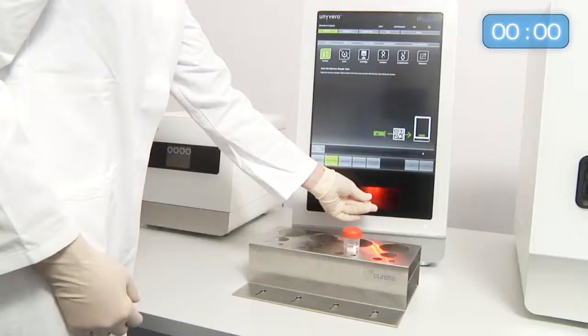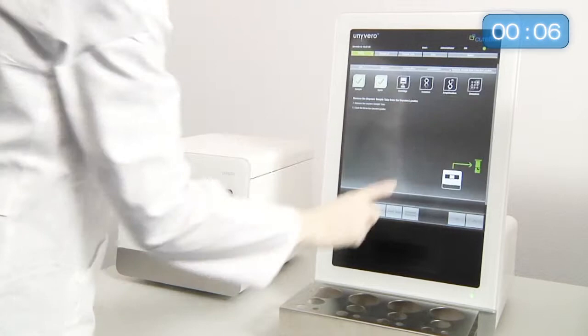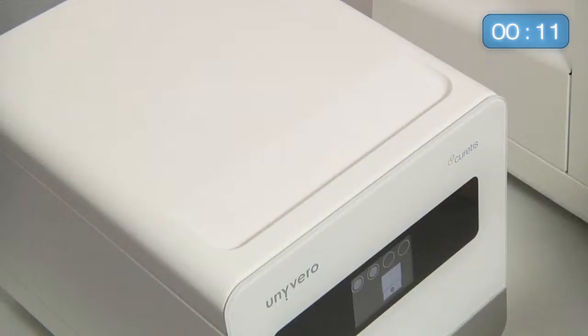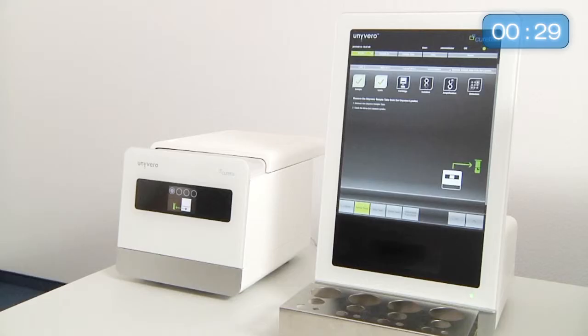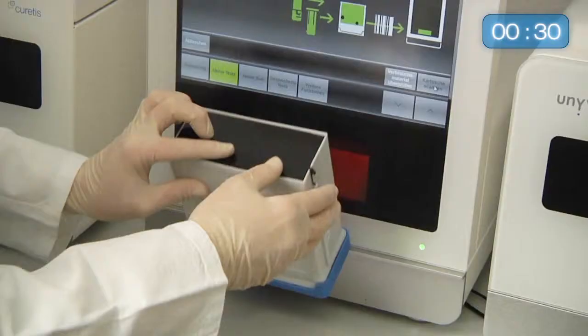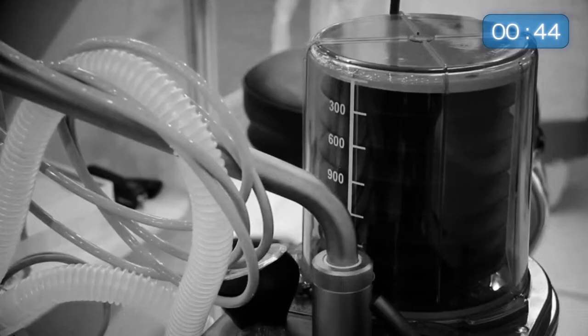The workflow starts by transferring the native patient sample into the sample tube. A fully automatic 30-minute lysis step follows inside the dedicated Lysator instrument. A huge variety of native clinical samples can be processed with a single protocol. After only 30 minutes, the sample tube can be taken out of the Lysator. Now the sample tube and master mix tube are inserted into the Unyvero cartridge, which is then inserted into the analyzer.